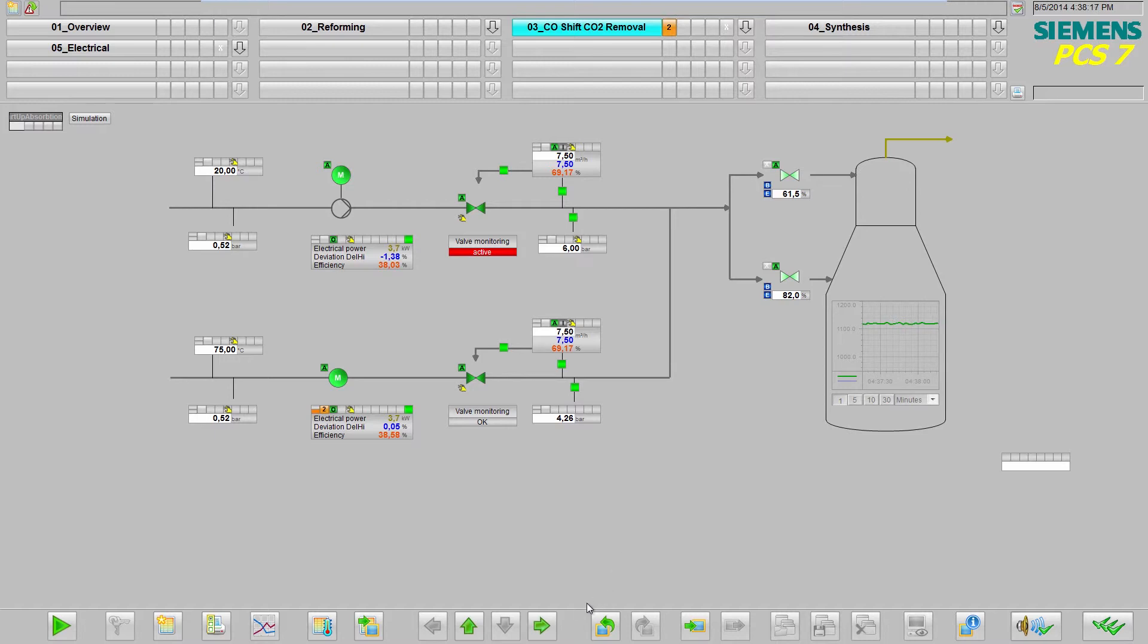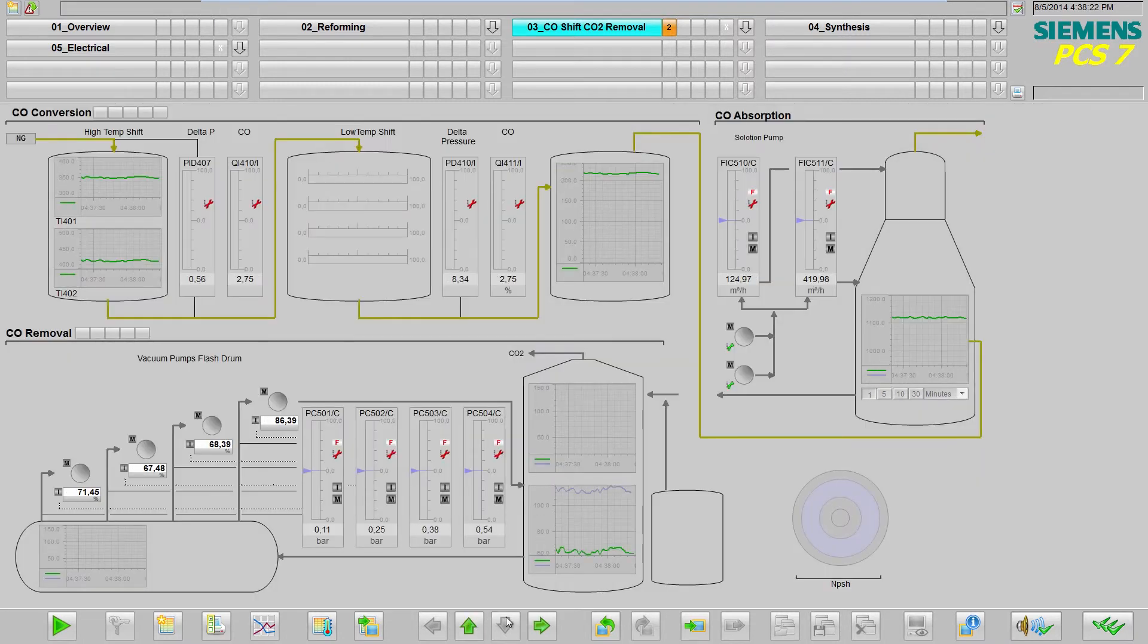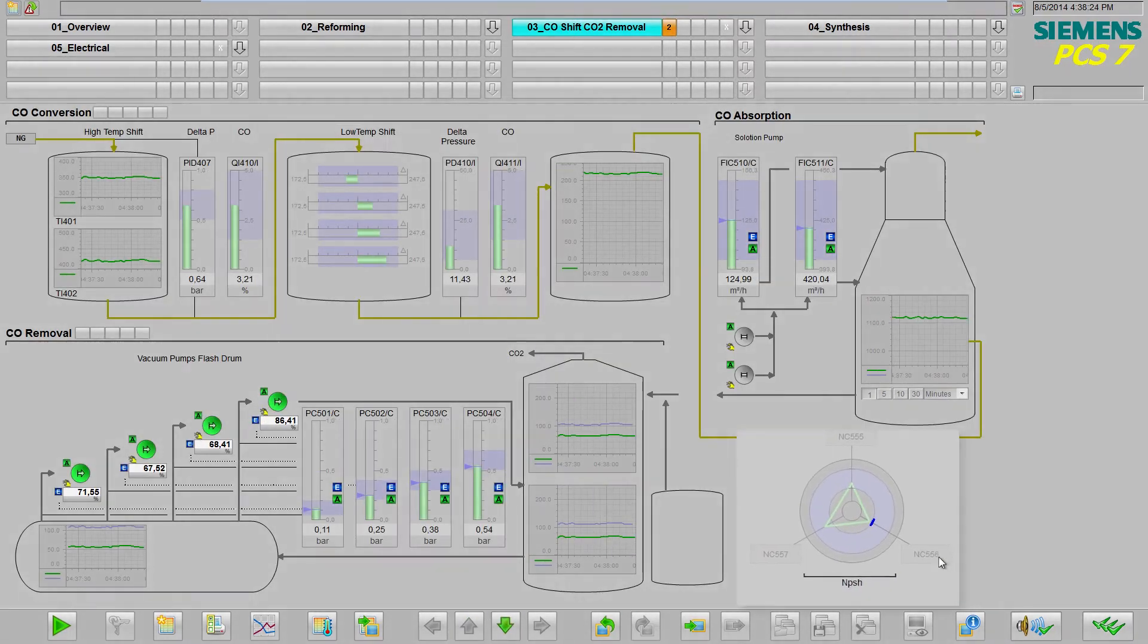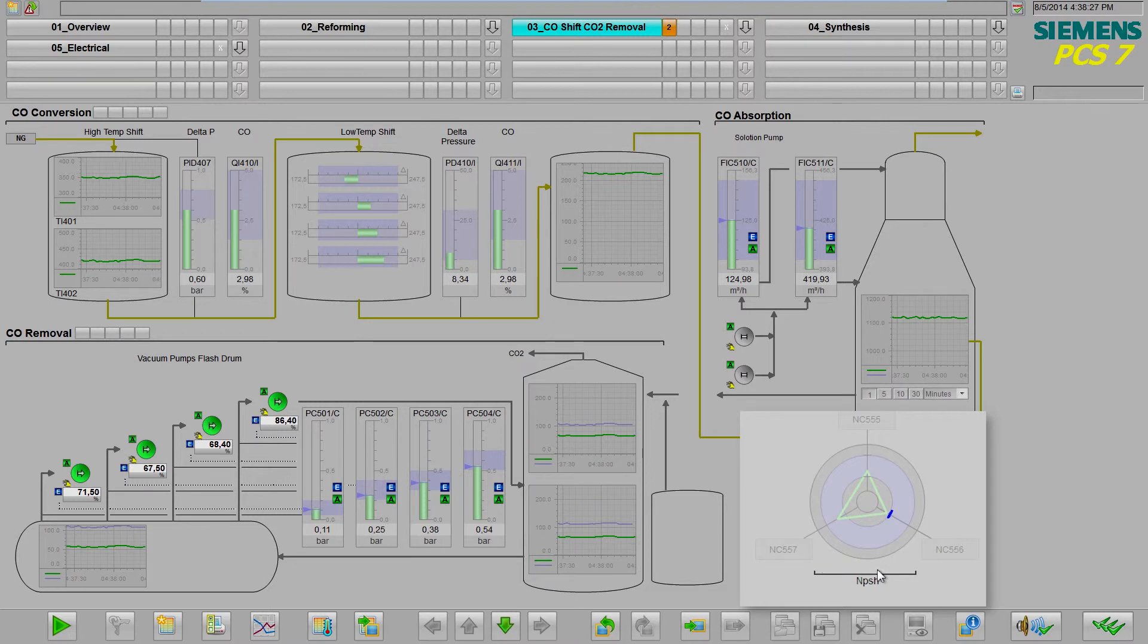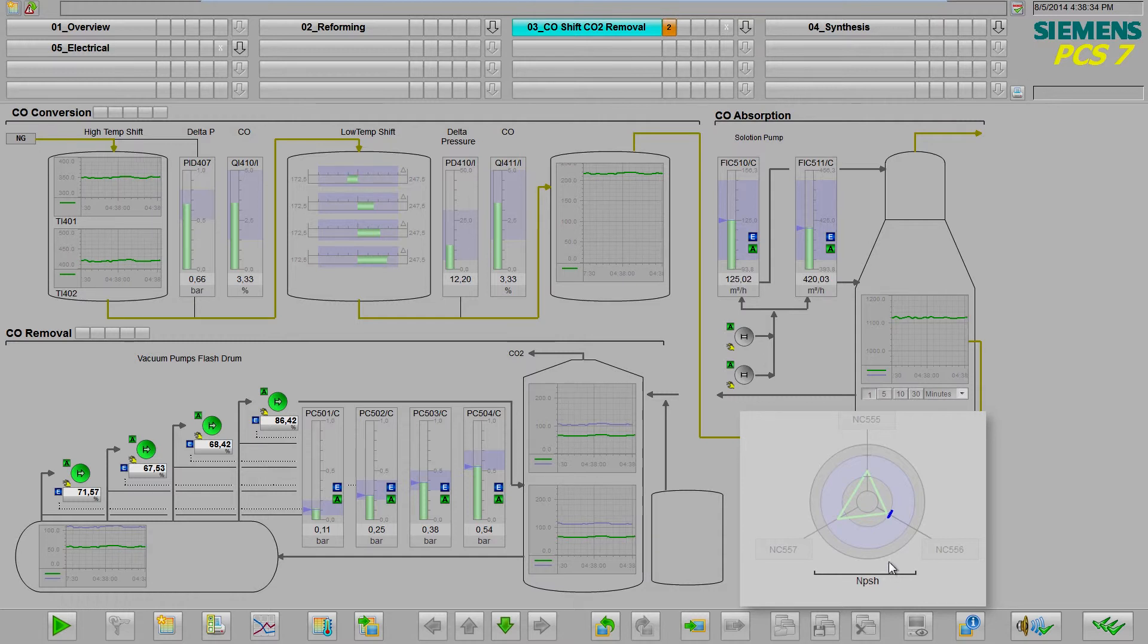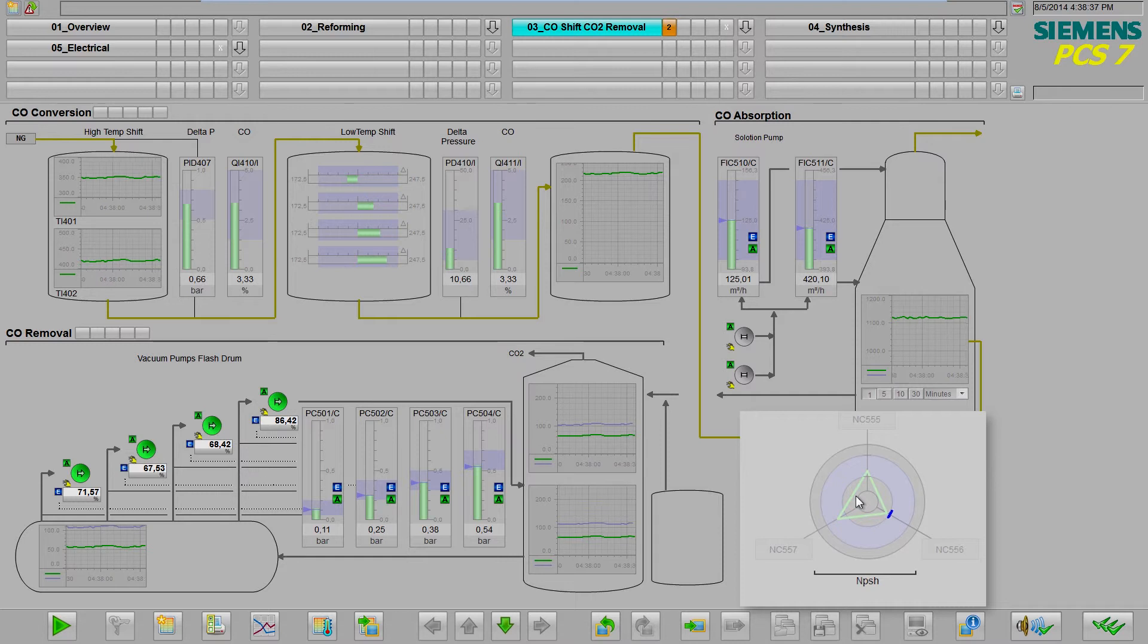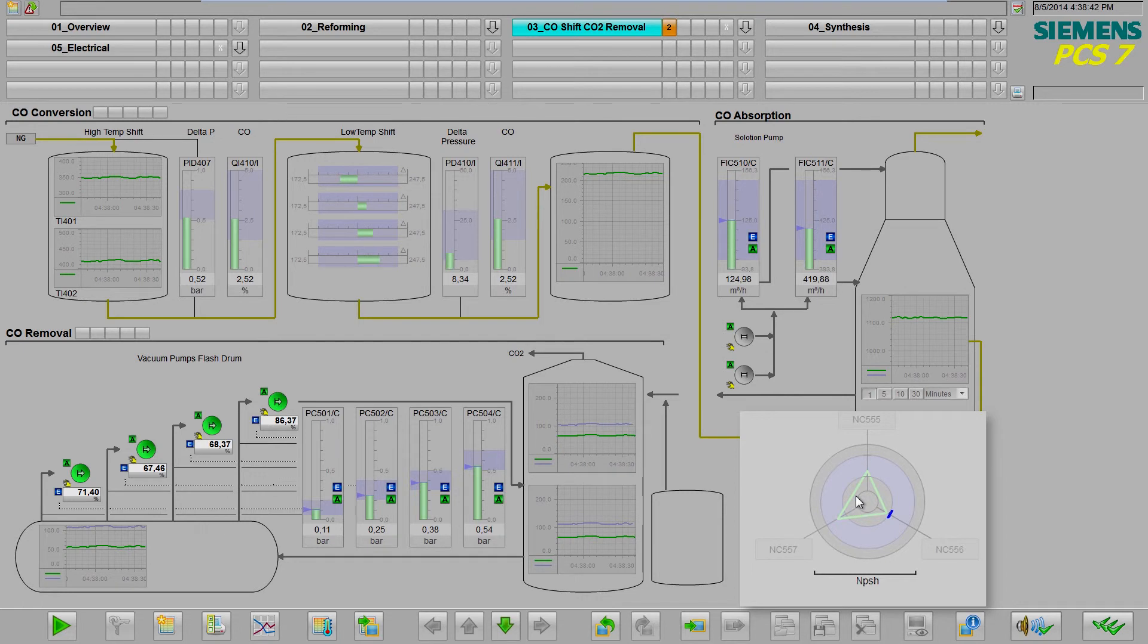Spider diagrams can be used to monitor several pumps in a single display. I am now going to show you a spider diagram in the overview. This allows deviations to be detected promptly through pattern recognition, and measures can therefore be taken to preserve the pump's lifespan. In this example, the blue bar reveals the onset of cavitation. If the cavitation increases, this will trigger an alarm.